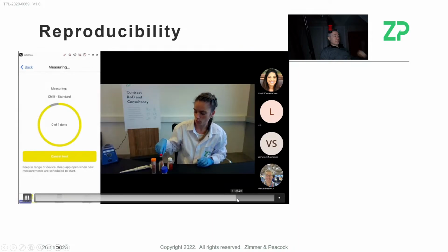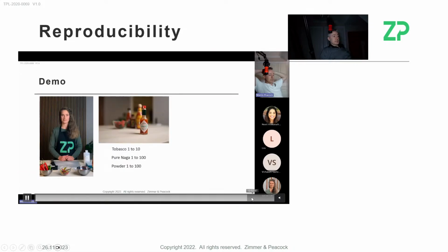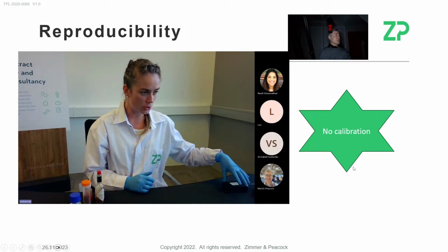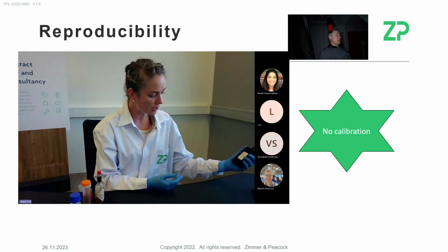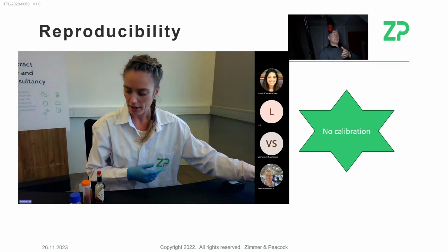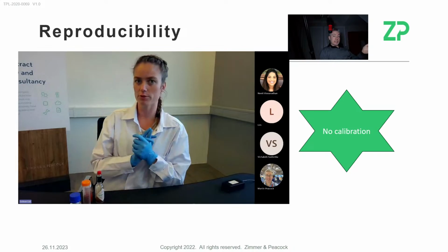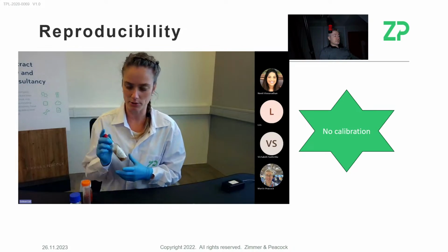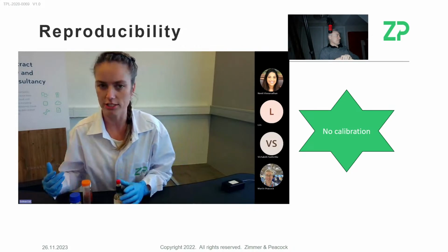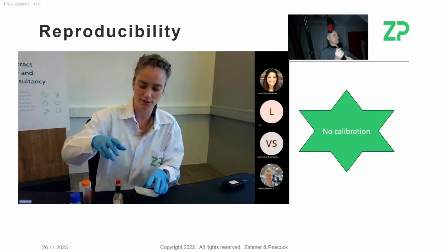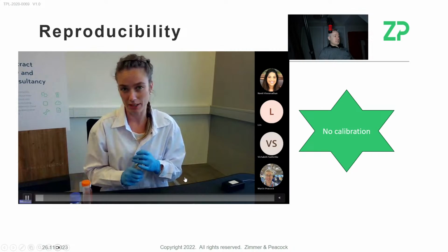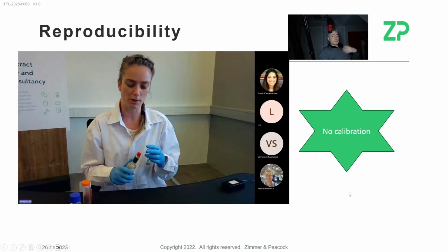This is the one for Chili. And what you'll notice is no calibration, and that's because of the reproducibility of our manufacturing. I must say it's easier to do non-calibration in an IVD application, in vitro diagnostic application, which this is really, rather than if you're trying to put a sensor onto a human body or into much more complex samples like tear fluid or blood or urine. Those are more challenging applications. An application like this is actually fairly straightforward, so we could do no calibration there.